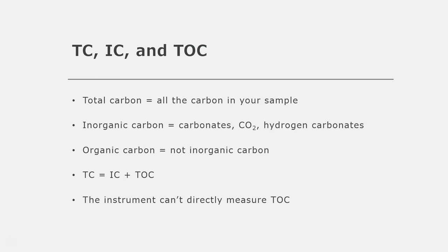Now let's talk about discerning between TC, IC, and TOC. TC means total carbon — it's all of the carbon in your sample. IC is inorganic carbon, which is all the carbonates, hydrogen carbonates, and carbon dioxide in your sample. TOC is total organic carbon, which is basically anything that isn't inorganic carbon. The main equation is TC equals IC plus TOC. This is useful because the instrument can't actually directly measure TOC. The instrument can measure total carbon by combusting the whole sample, and it can measure inorganic carbon by acidifying the sample and sparging out the CO2. It can then subtract the inorganic carbon from the total carbon to give you a result for TOC, but it's not actually directly measuring total organic carbon. Measuring TOC can be tedious because you have to measure both TC and IC, which means two calibration curves, and the run takes longer.